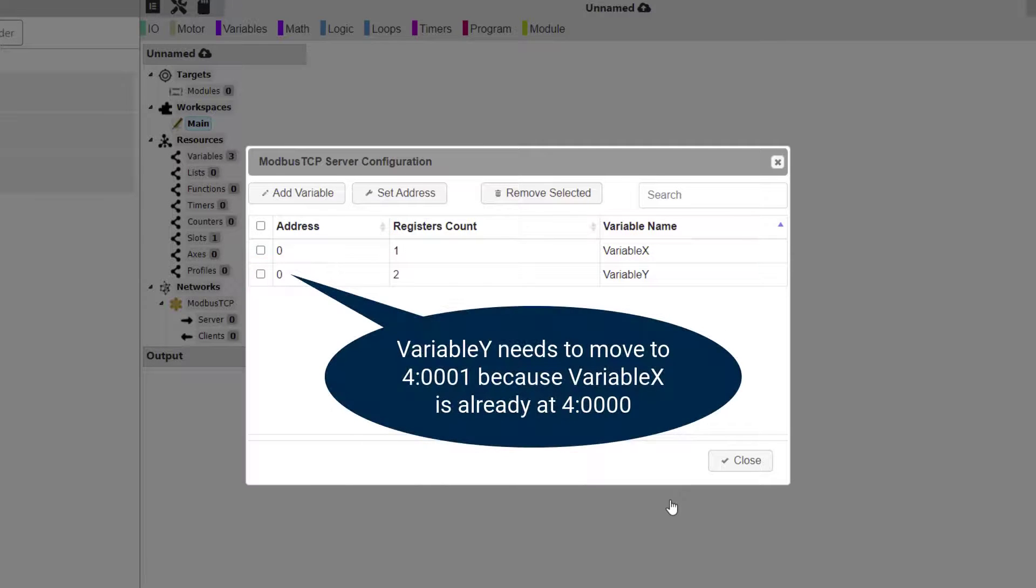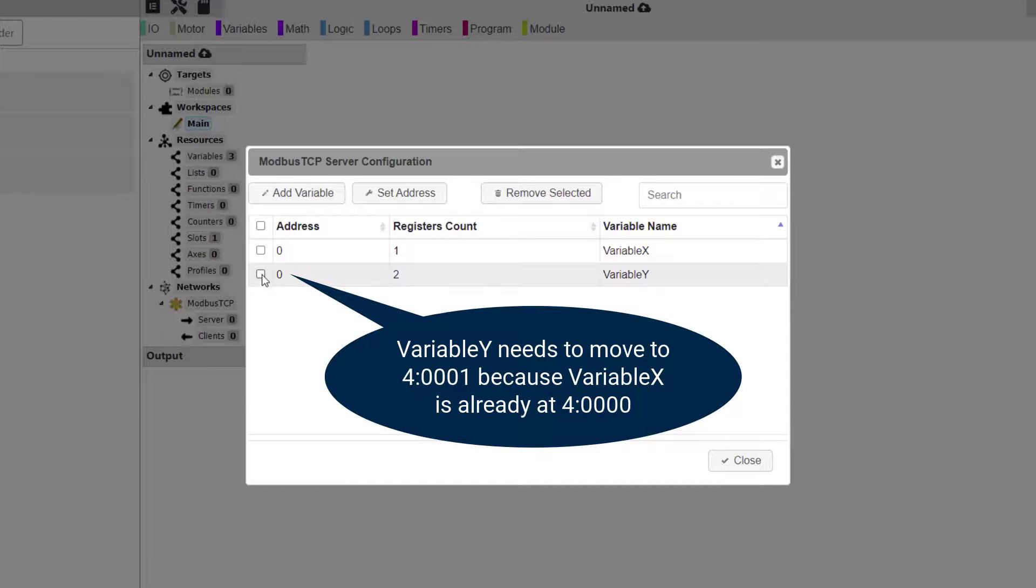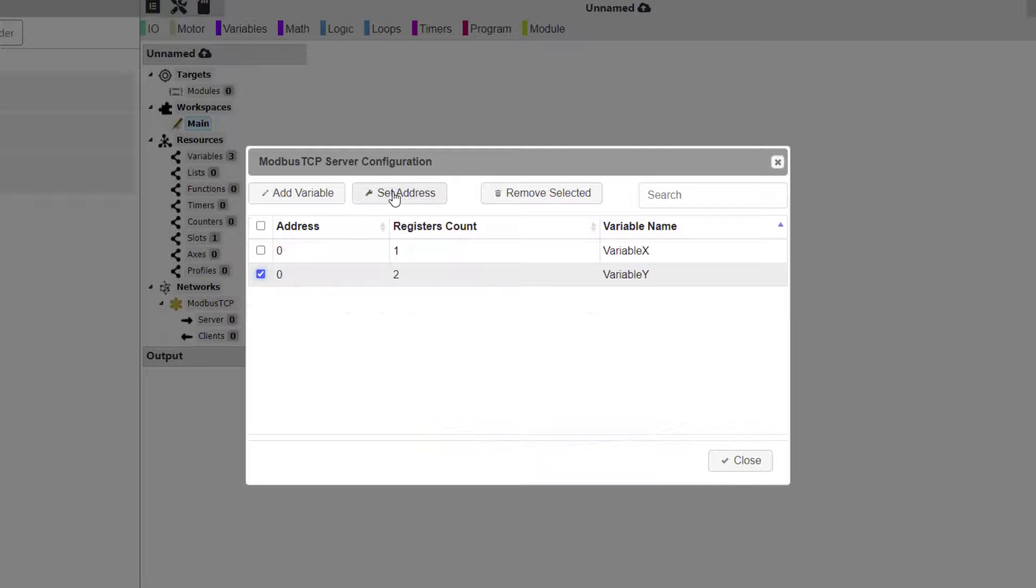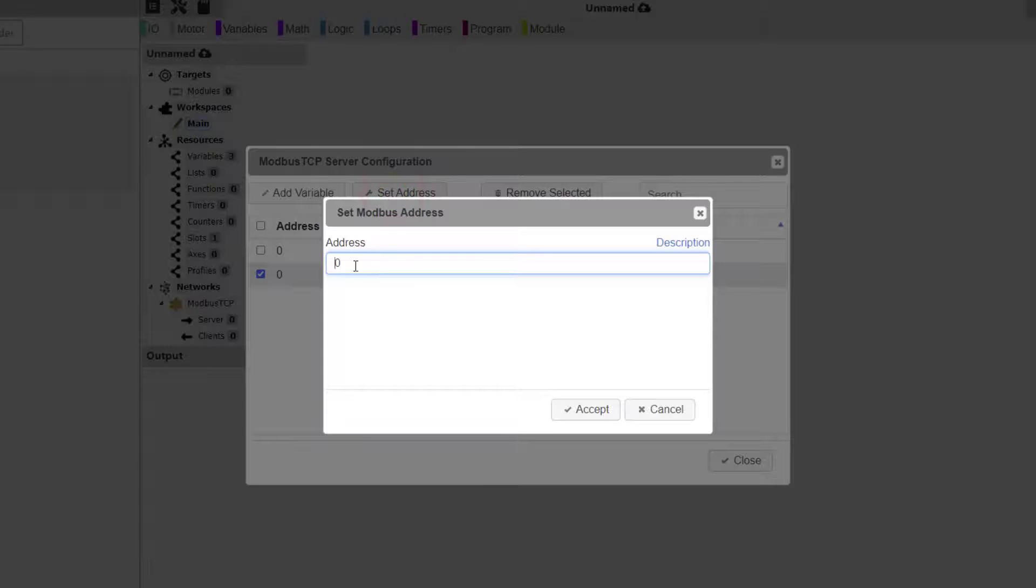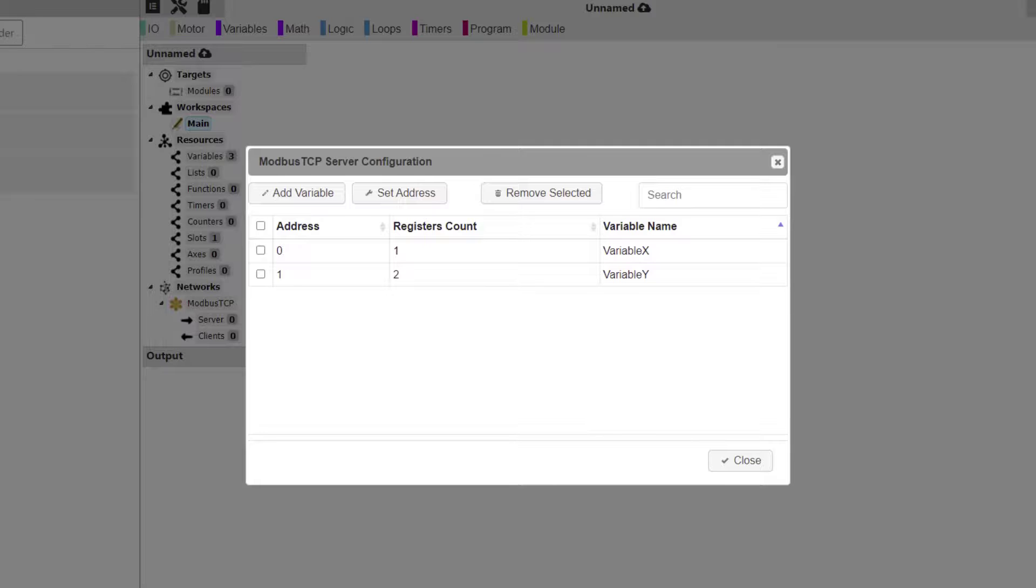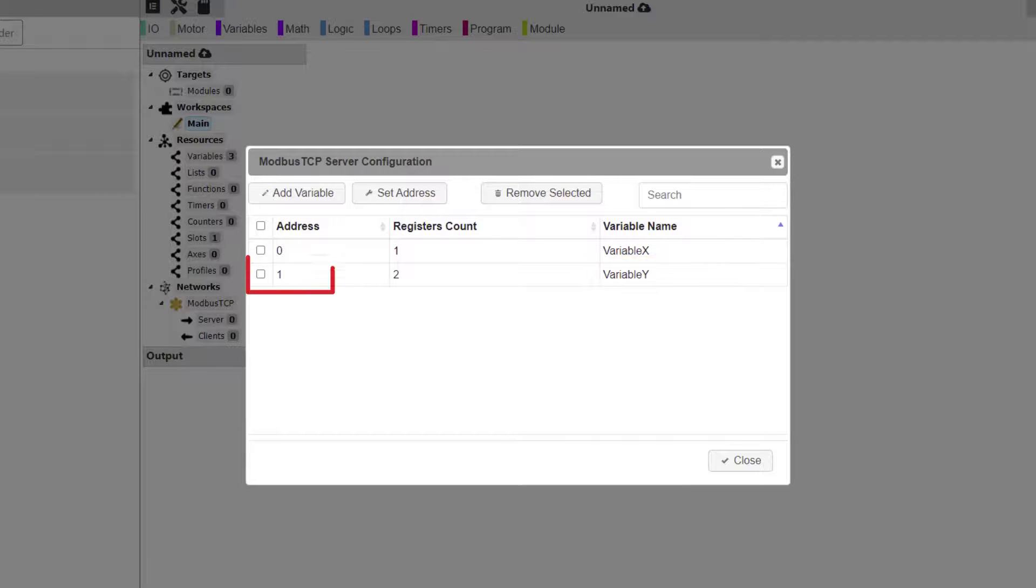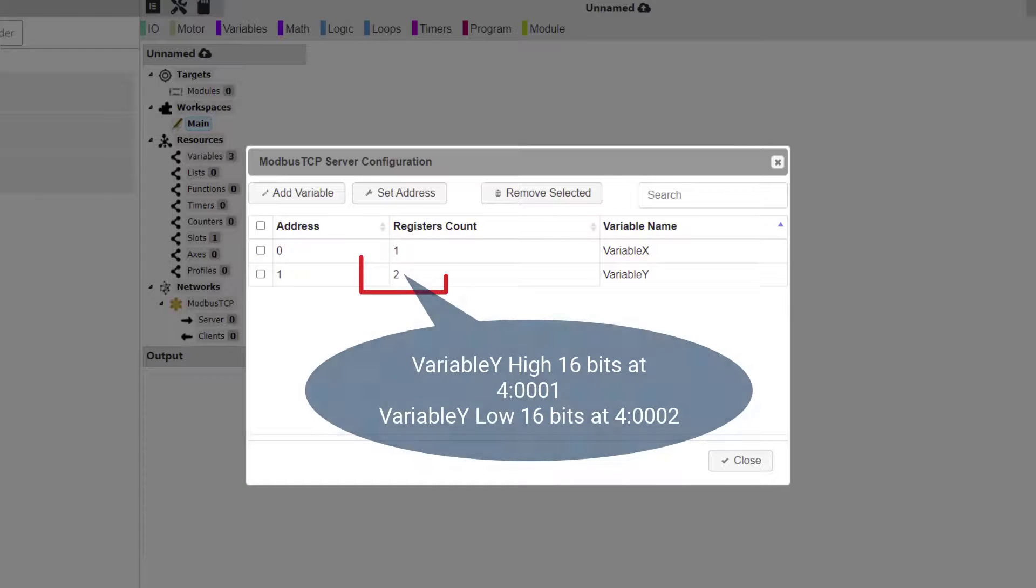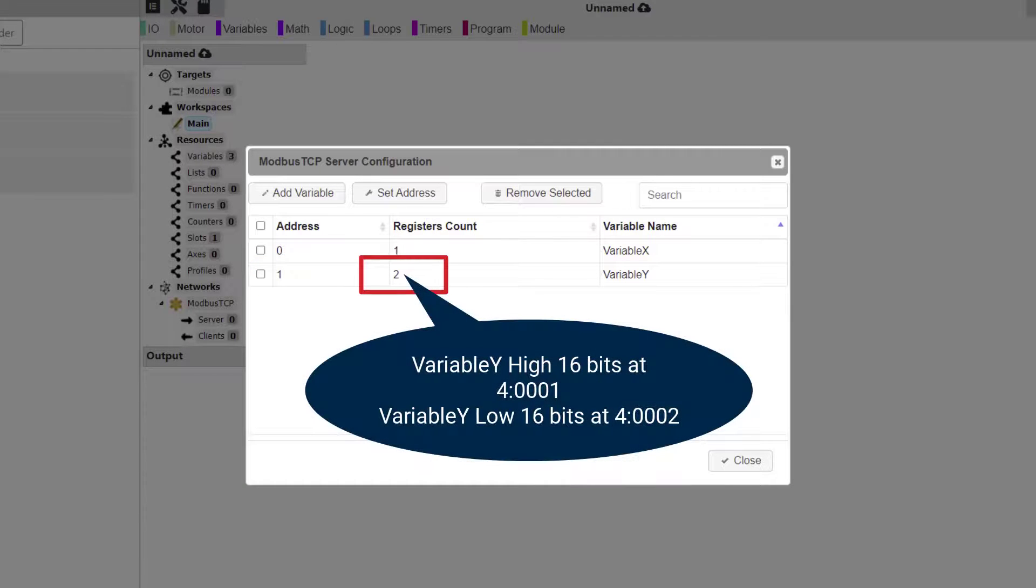We need to change this to Holding Register Address 1. Click Set Address button and Enter 1, and then click Accept. Now we can see that Variable Y has been assigned to Holding Register 1 and that the Holding Register count for this variable is 2 because it is a double integer data type.